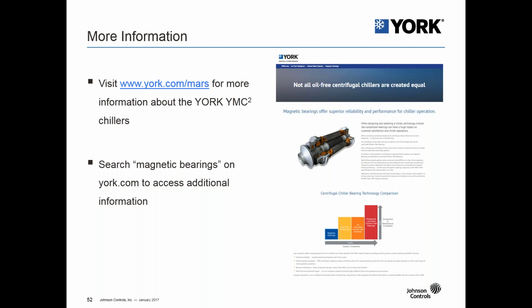So the last question here is, is the compressor motor located outside of the refrigerant loop? For the York YMC squared chiller, it is a refrigerant cooled motor, so it is inside of the chiller package. It's a semi-hermetic motor.